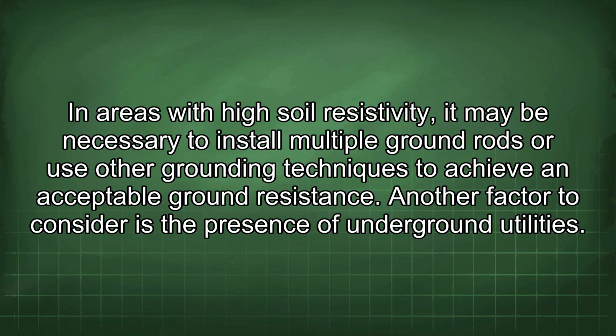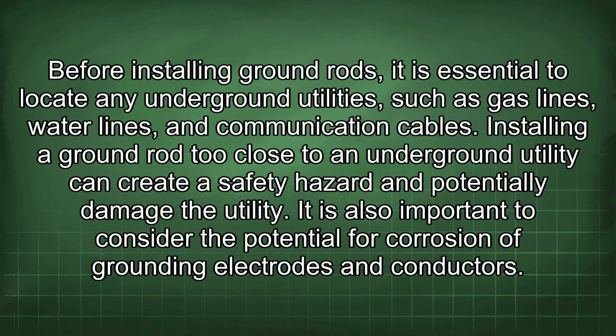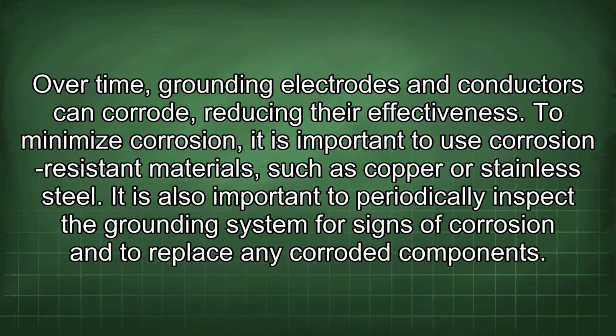Another factor to consider is the presence of underground utilities. Before installing ground rods, it is essential to locate any underground utilities, such as gas lines, water lines, and communication cables. Installing a ground rod too close to an underground utility can create a safety hazard and potentially damage the utility. It is also important to consider the potential for corrosion of grounding electrodes and conductors. Over time, grounding electrodes and conductors can corrode, reducing their effectiveness. To minimize corrosion, it is important to use corrosion-resistant materials such as copper or stainless steel. It is also important to periodically inspect the grounding system for signs of corrosion and to replace any corroded components.